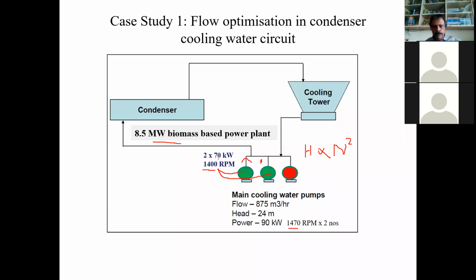The inlet temperature of the condenser is 28 degrees centigrade, outlet 36.7. Most power plants have a cooling tower range of even 10 degrees. So this cooling tower was designed for a range of 10 degrees. Here 28 is going, 36 is coming. Still there is a possibility of increasing the range. Now the delta T is 8.7 degrees.